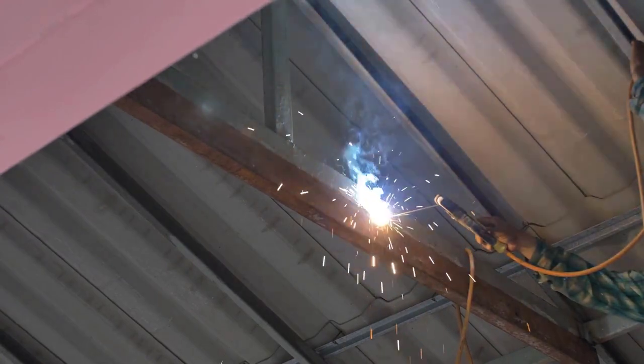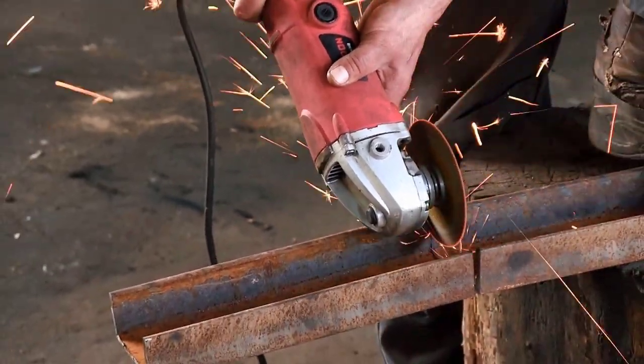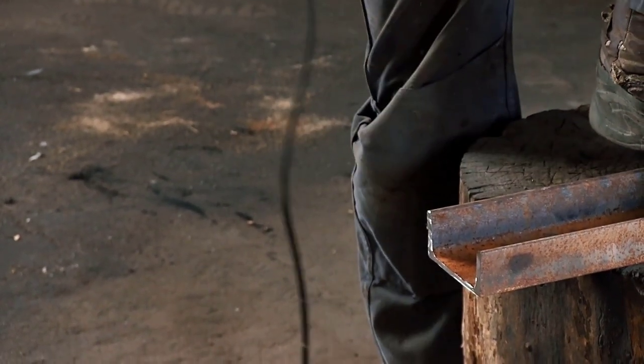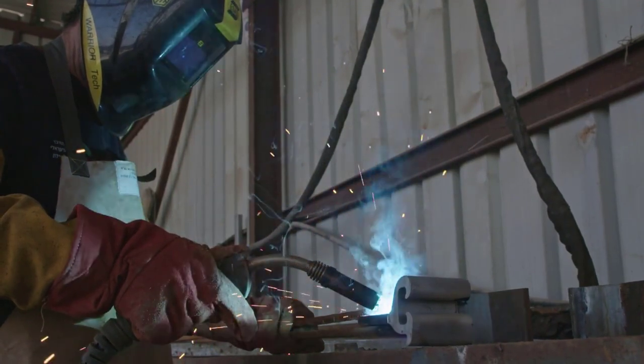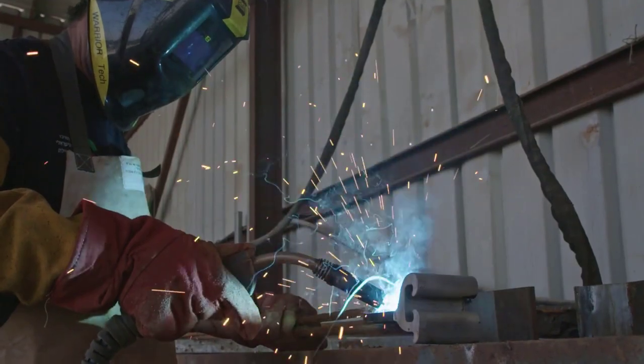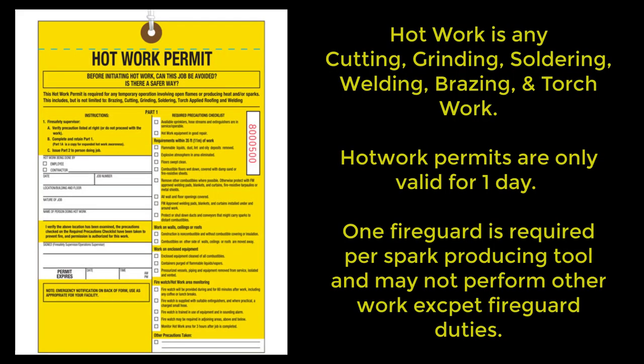Hot work permits are to be issued daily. The responsible person issues the hot work authorization form. A pre-check should be done prior to the start of work. One fire guard is required per spark producing tool and may not perform other work except fire guard duties.